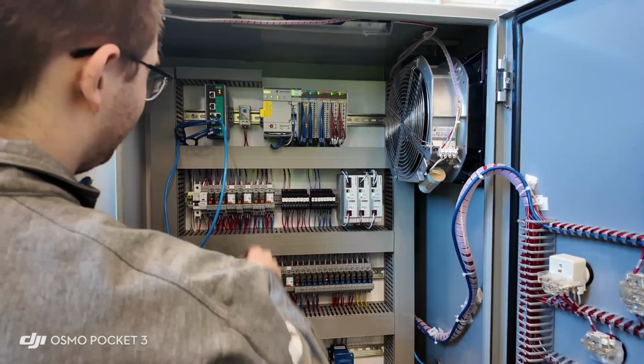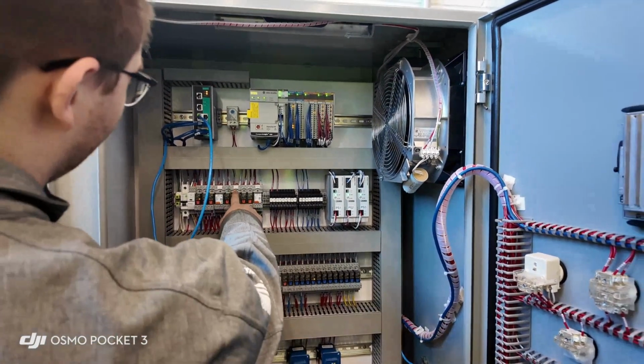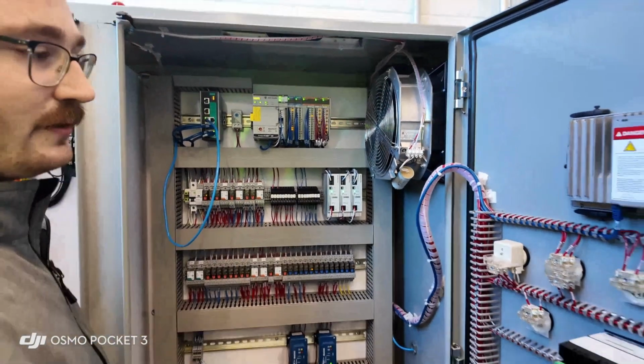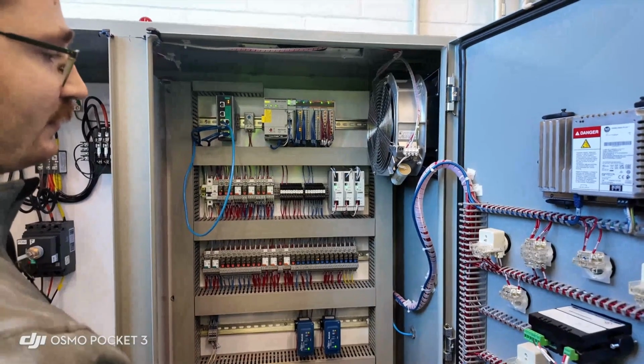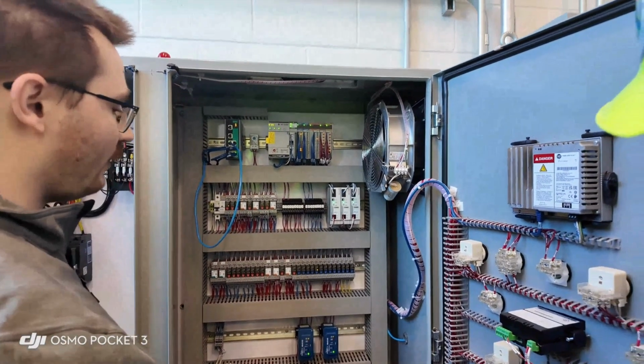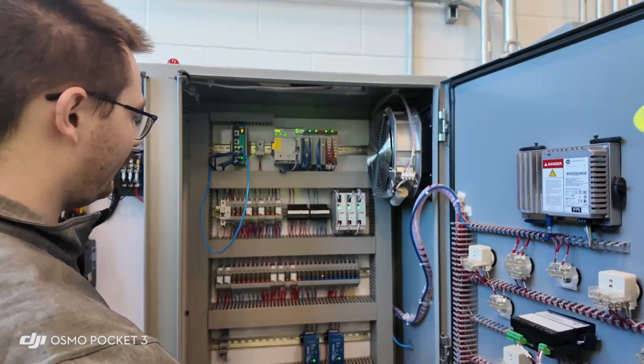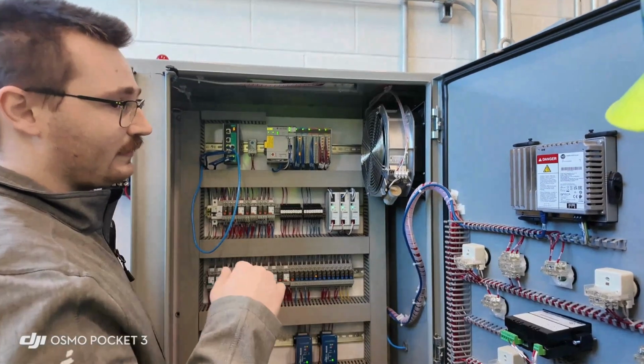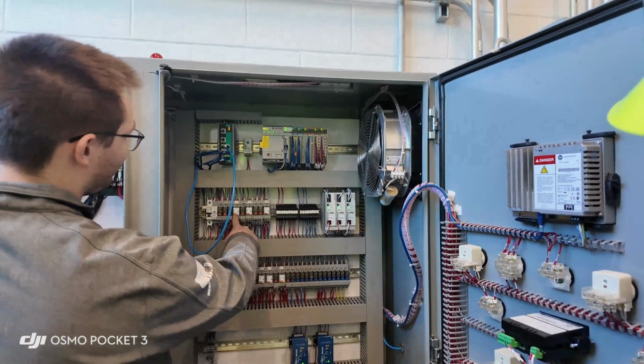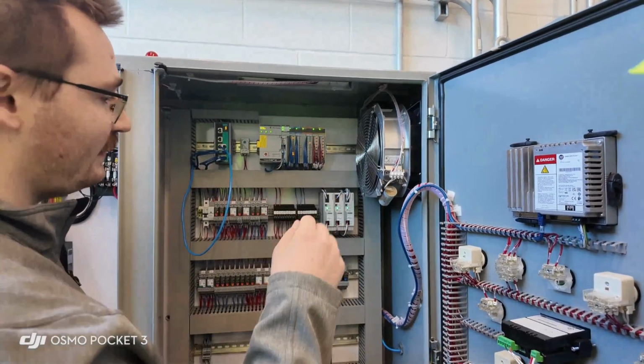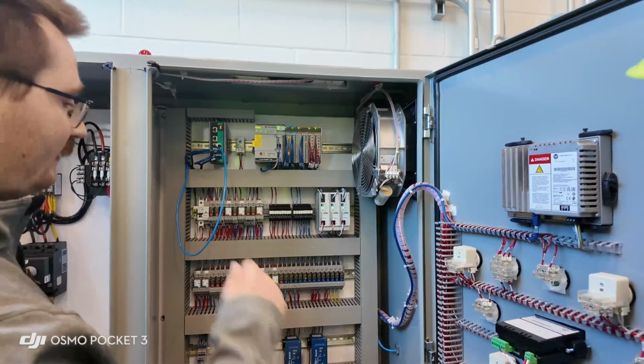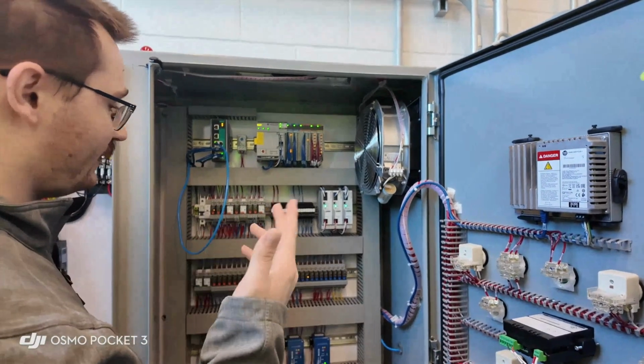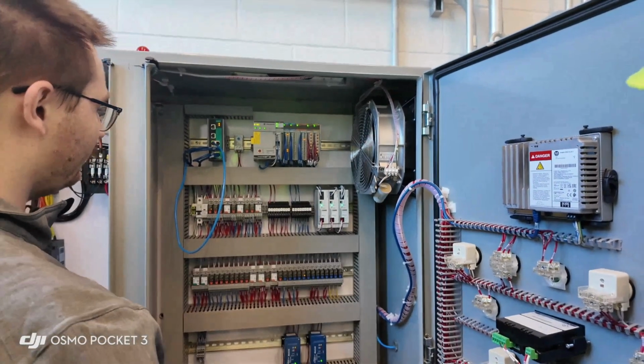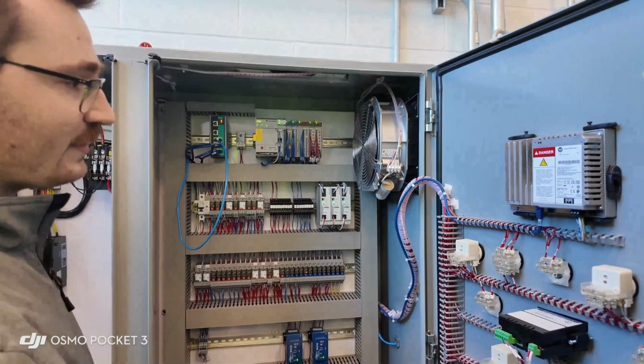Next up is your level set point 1 and your level set point 2. This is for the backup control. So say your transducer goes down and the water in the well keeps filling. It's going to hit level set point 1, and it'll keep going to level set point 2, and then it'll hit the LSHH. Once the LSHH kicks on, it's going to allow the backup circuit to start running, and it's going to start both pumps, pump down to the low level, the LSL, and the low level is going to open that circuit, and it's going to break it.